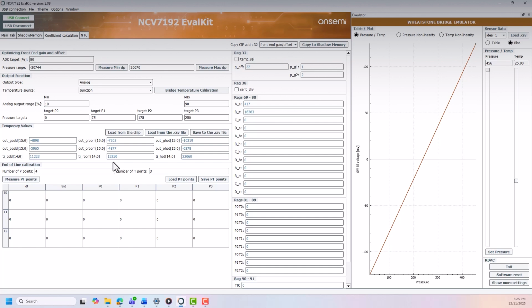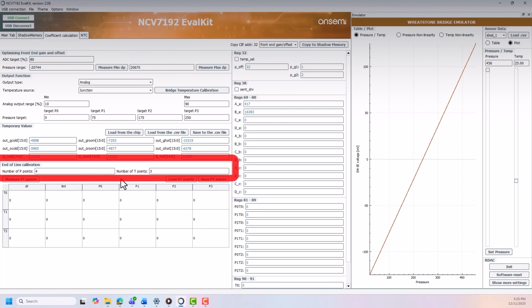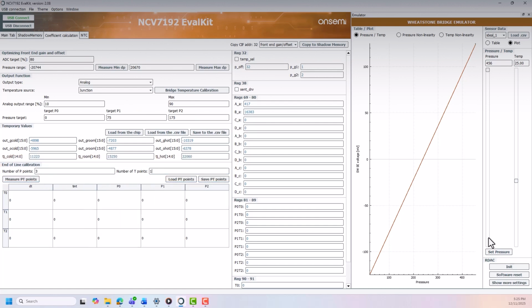Now let's move to strobing pressure and temperature points. We can strobe maximum 4 pressure points at 3 temperatures, but for simplicity, we will use less points. In this field, we select, for example, that we want to calibrate on 3 pressure points, and here we set just 1 temperature point. When we move with the emulator slider, you can see that the selected emulated sensor values goes from value 20 to value 456. This is no unit in the software. Just ratio between these values is important.